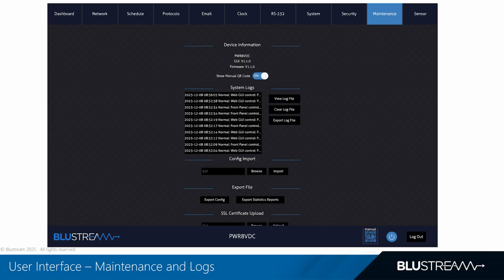The maintenance tab here is your service hub. At the top, you'll see system logs, a time-stamped record of configuration changes, power events, overload and warning states, and user interactions. That audit trail is invaluable when you're investigating a power outage, validating who changed what, or documenting a site handover. You can view, clear, or export these logs directly from this page.